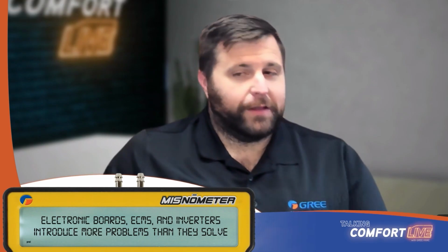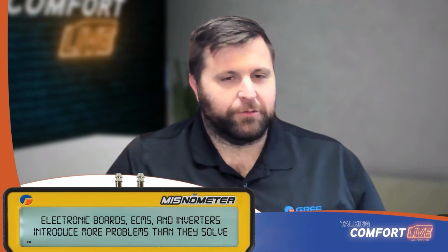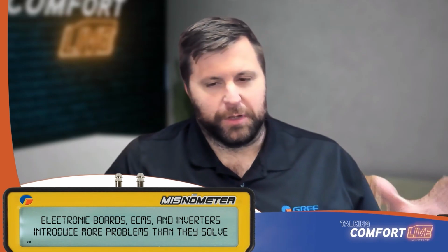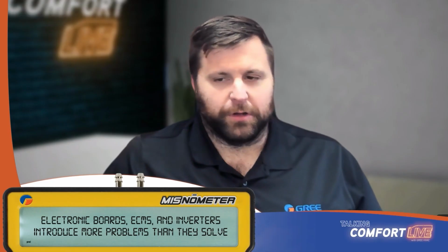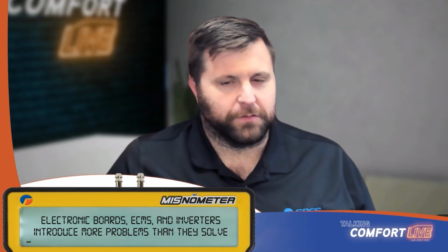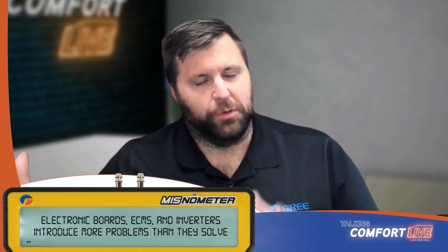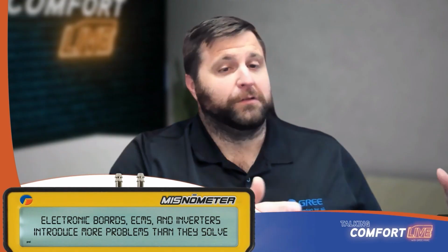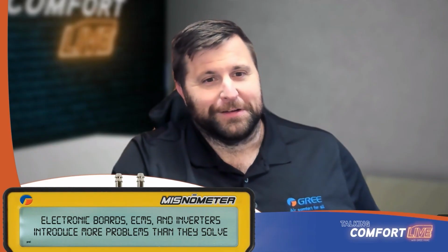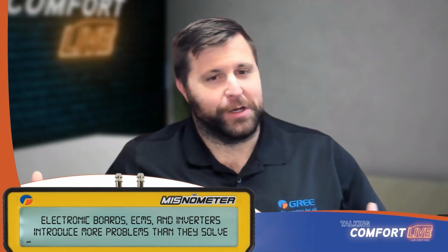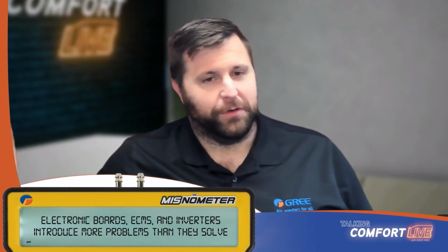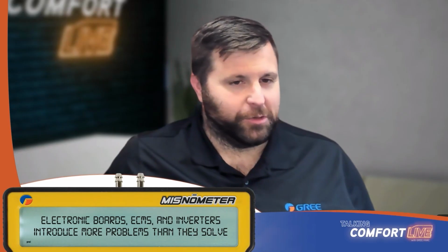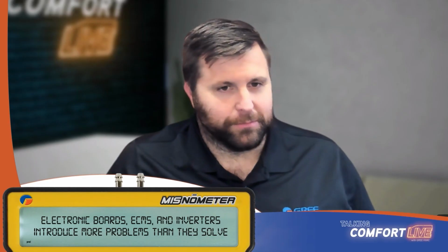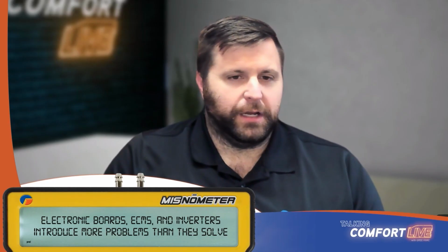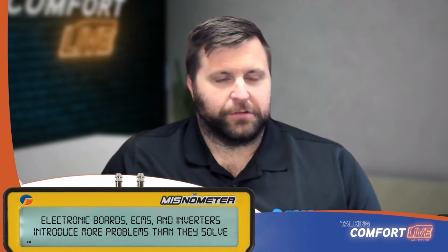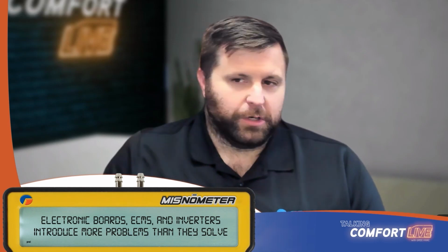One of the reasons that changed was to have a more realistic test. We kept increasing the minimum SEER ratings and all that. Well, it turns out that because we changed the way we designed our duct systems, we took those slightly more efficient units and made them probably less efficient than the previous lower efficiency units. Because you take a unit that was rated at 0.1 static pressure and put it on a duct system that's 0.5, is that going to be the same efficiency? No, obviously not. You had equipment out there that was discontinued because it no longer hit the minimum SEER ratings. So we had to make that adjustment.